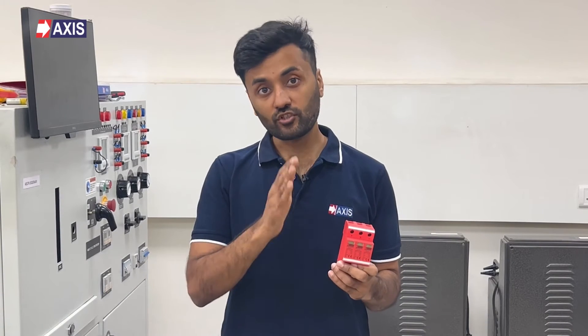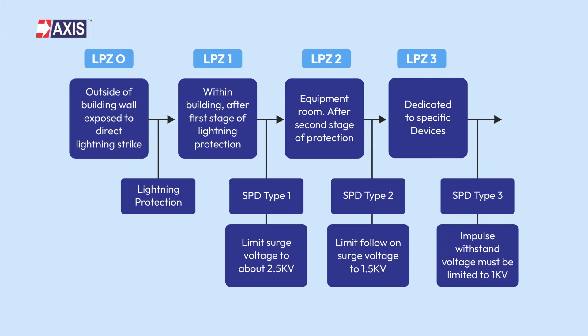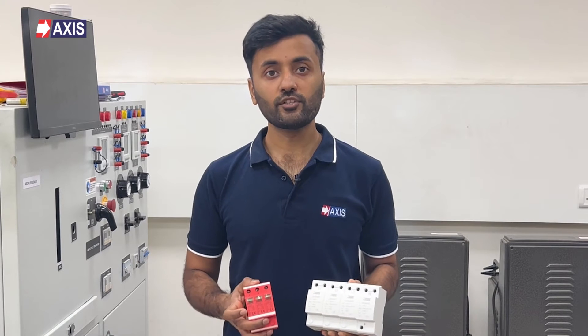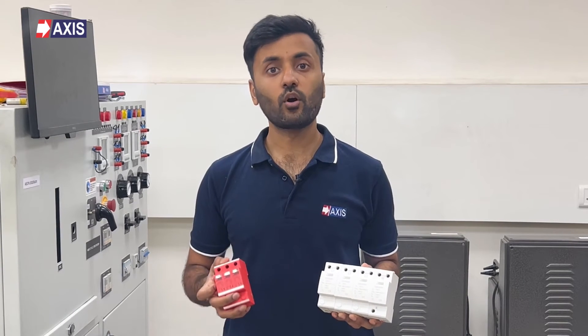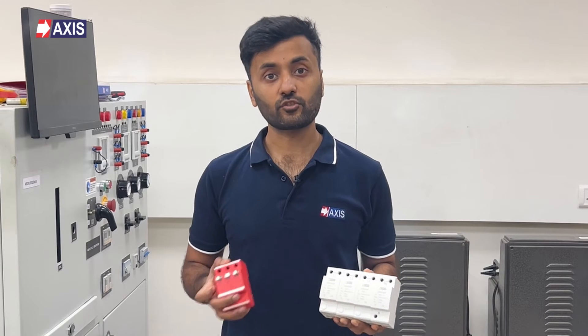Surge protection devices are used in areas where a transition takes place between two different lightning protection zones, as shown in this flowchart. For example, a Type 1 or Type 2 SPD would be used at the main power distribution switchboard where the electrical system enters the structure. For more information on lightning protection zones, please read our blog on the topic — the link is in the description.